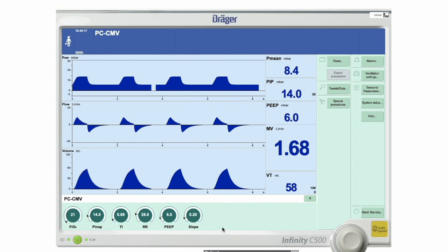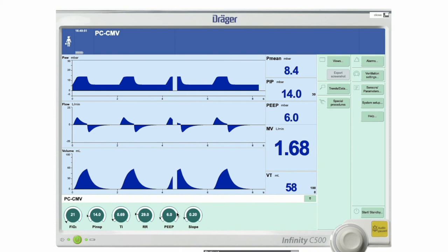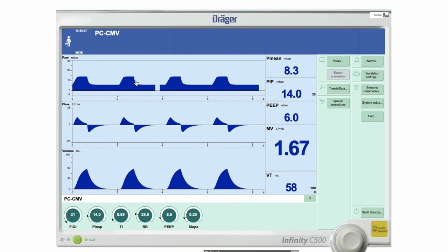Anytime you make a change, come back and see what you're left with. The slope button — which you have in pressure modes but not volume modes — is an inspiratory rise time. It controls how long it takes for the pressure to go from PEEP to PIP during inspiration. With an inspiratory time of approximately 0.7 seconds, 0.2 of that is the rise time and 0.5 is the sustained time.